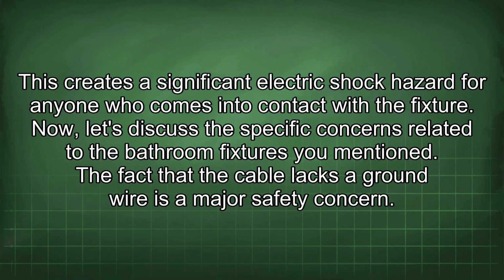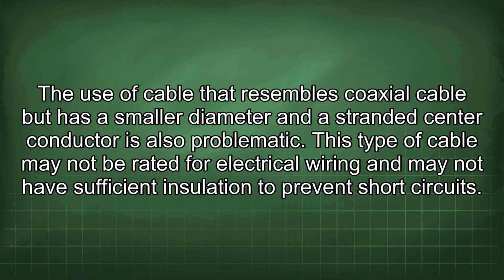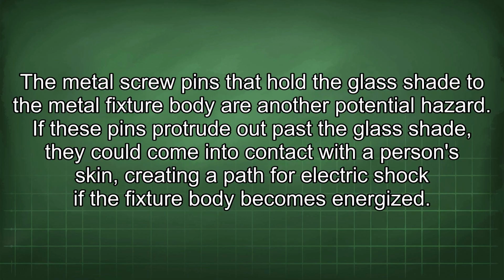Now, let's discuss the specific concerns related to the bathroom fixtures you mentioned. The fact that the cable lacks a ground wire is a major safety concern. The use of cable that resembles coaxial cable but has a smaller diameter and a stranded center conductor is also problematic. This type of cable may not be rated for electrical wiring and may not have sufficient insulation to prevent short circuits. The metal screw pins that hold the glass shade to the metal fixture body are another potential hazard. If these pins protrude out past the glass shade, they could come into contact with a person's skin, creating a path for electric shock if the fixture body becomes energized.